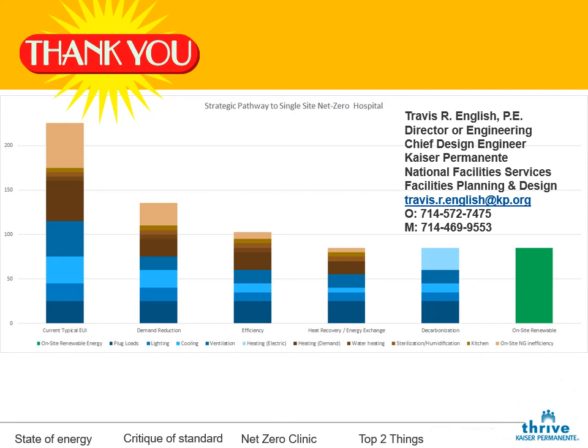But when you actually look at the system data, the outside air temperature is 70 degrees, the room temperature is 70 degrees, and the supply air temperatures are 70 degrees. And I mean, like everywhere, there's just no load. And my theory is that that's not uncommon at all. In hospitals, we have a lot of hours per year where our spaces are pretty quiet and we're burning energy during those times. If you want to design an energy efficient hospital, design it for 3 o'clock in the morning in the spring or 3 o'clock in the morning in the fall when it's 70 degrees outside and there's no solar load. And then commission it for that time period.